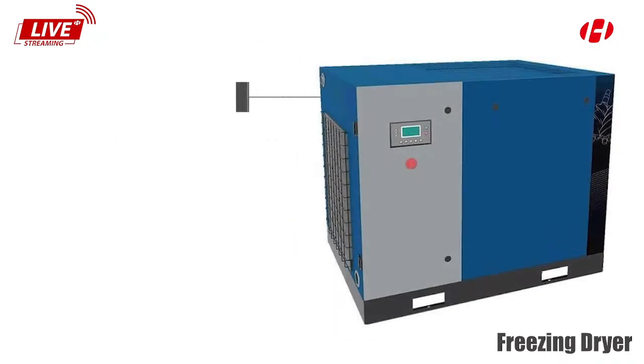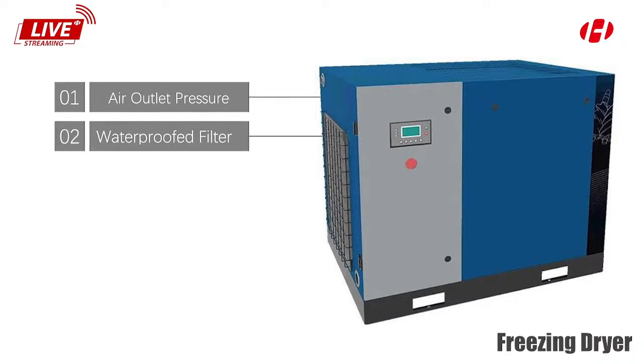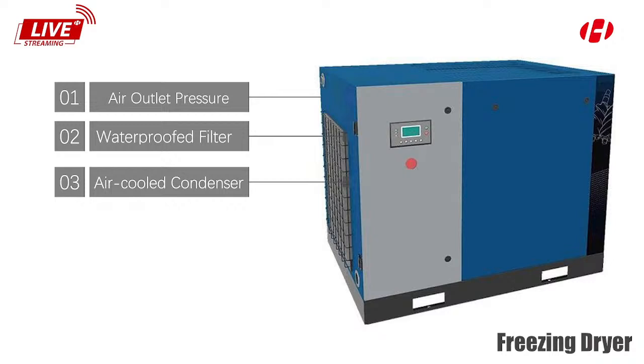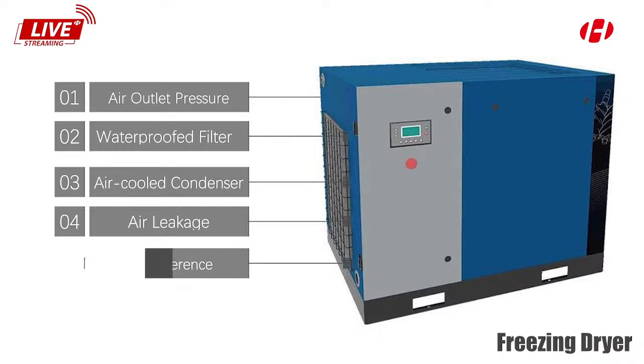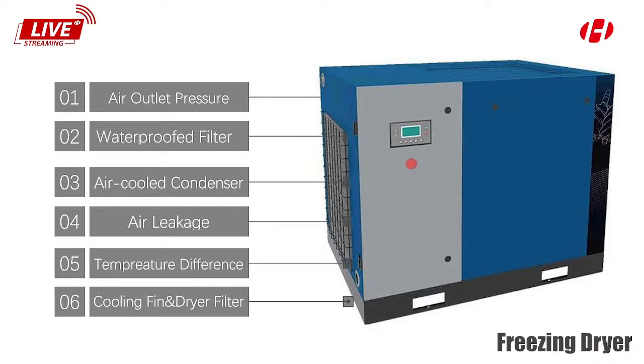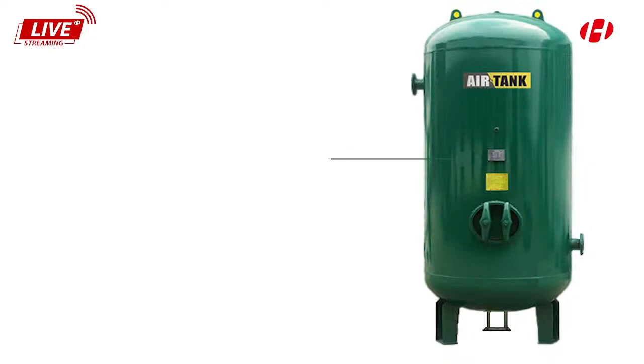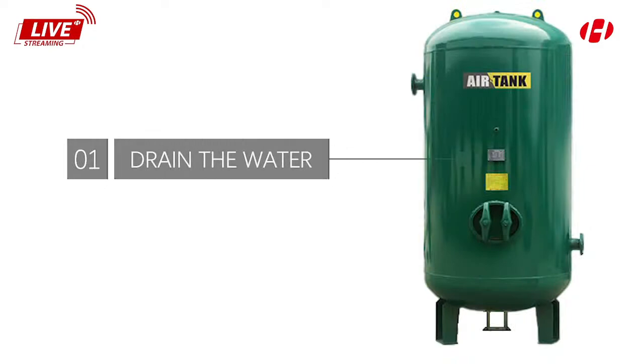Freezing dryer. Daily check whether the air outlet pressure of the freezing dryer is normal. If it's less than 4 bar, there is a possibility of blockage. Each filter needs to be drained of water at regular intervals. Weekly blow-through of the air-cooled condenser with a compressed air gun. If the environment around the machine is dusty, increase the number of blowing sessions as appropriate. Weekly check of air leakage from the dryer interface. Check the temperature difference between the air inlet and outlet of the dryer every month. Clean the cooling fin. Check or replace the dryer filter every 6 months. Gas holder: drain the water before starting or finishing work each day.